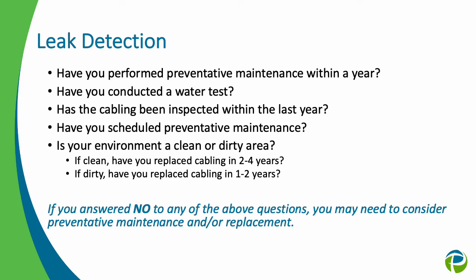But leak detection does need to be replaced pretty frequently. So if we're talking about your leak detection and thinking, do I need to replace it or factor replacement for next year, we're going to ask, have you performed preventative maintenance within a year? Have you done a water test? What we mean by that is, if you have water leak detection, have you had someone put some droplets of water on the cable in a few different spots and see the system detect it? Are you making sure the system's working? Because you can't just leave it and hope it works. You need to test it every once in a while.